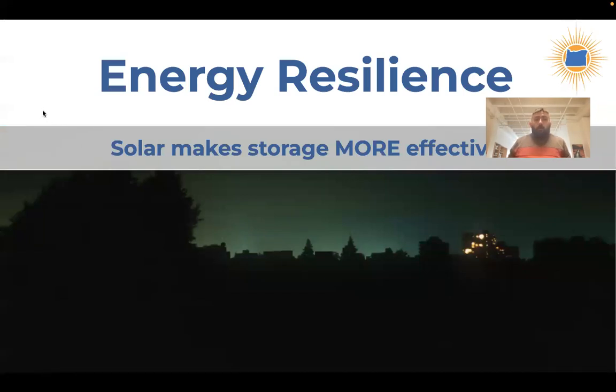So I'm going to debunk a little myth here. Solar itself, if you just have a home or a business and you install solar on it and the power goes off in your neighborhood, you cannot use the energy from your solar panels. Even in the daylight, even if it's producing electricity, and that is because of a national electrical code requirement that your system be shut off from the wider grid, and it turns the system off.